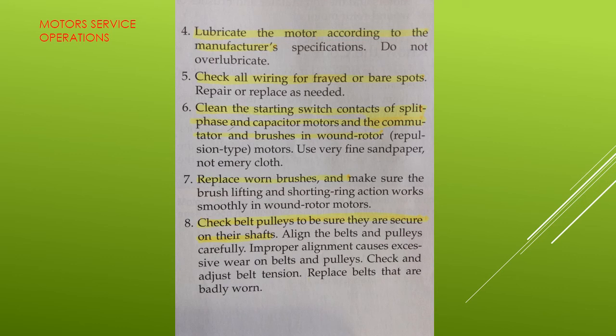Step eight, check belt pulleys to be sure they are secure on their shafts. Align the belts and pulleys carefully. Improper alignment causes excessive wear on belts and pulleys. Check and adjust belt tension. Replace belts that are badly worn.